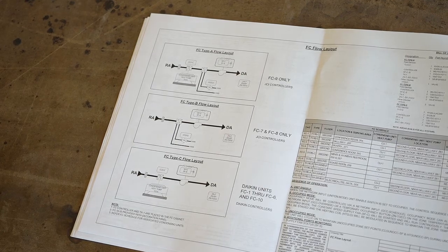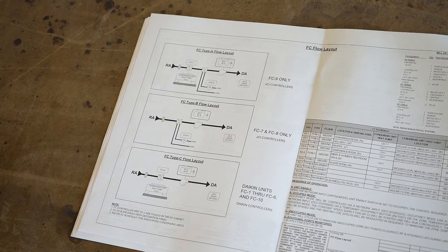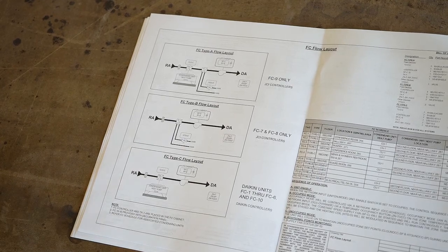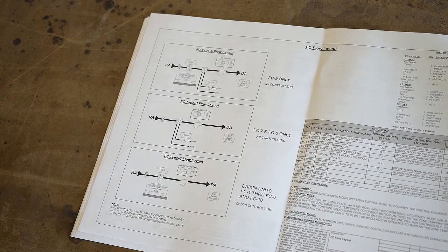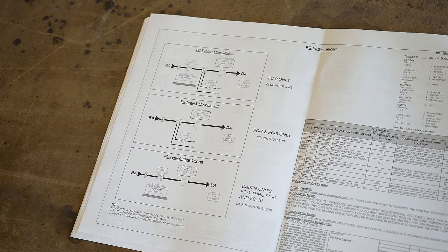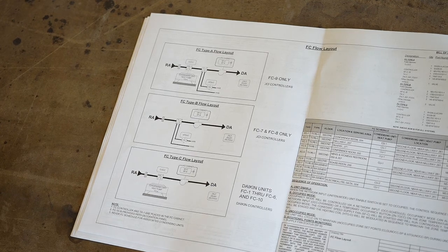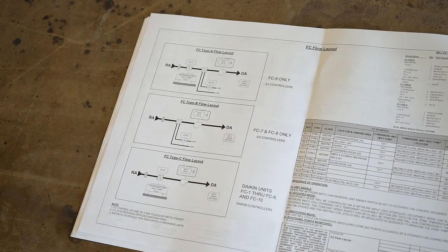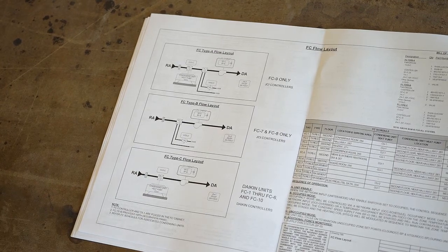Even the one in the basement in the IT room, that's the end of line downstairs. So you daisy chain to the main cassette unit, which is the one that hangs from the ceiling and blows the air in. And then you also have a Daikin thermostat on the wall, which would be the same as this one over here. Then you have a wire going from those thermostats up to the cassette unit in the ceiling, okay? And those are all 18 two-stranded non-shielded wire. Just FYI, if you have to replace a wire, it's very critical that you use that same wire, okay?